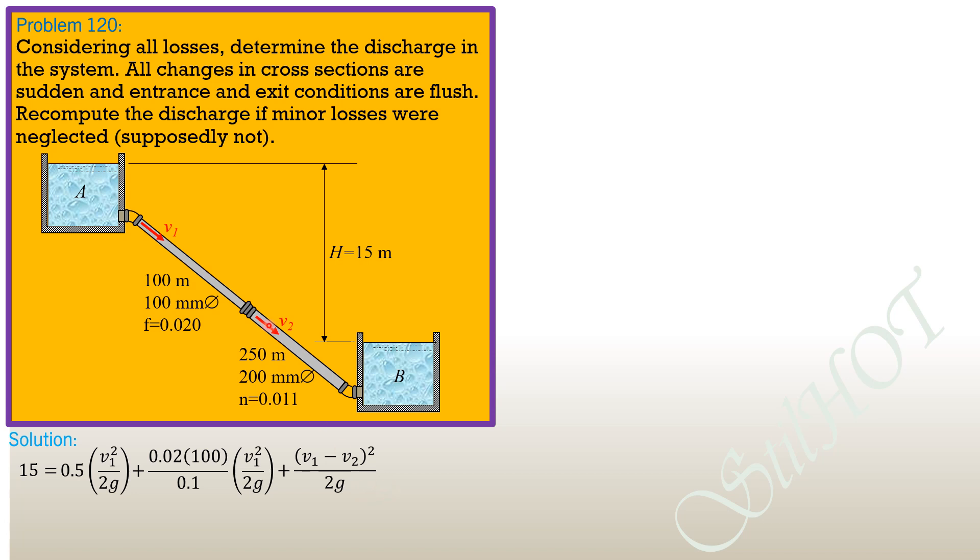Then plus head loss due to pipe friction in this pipe by Manning's formula, 6.35 N square, so 0.011 square, length 250, velocity square over diameter to the 4 thirds. So velocity is V2 square over diameter 0.2 to the 4 thirds.